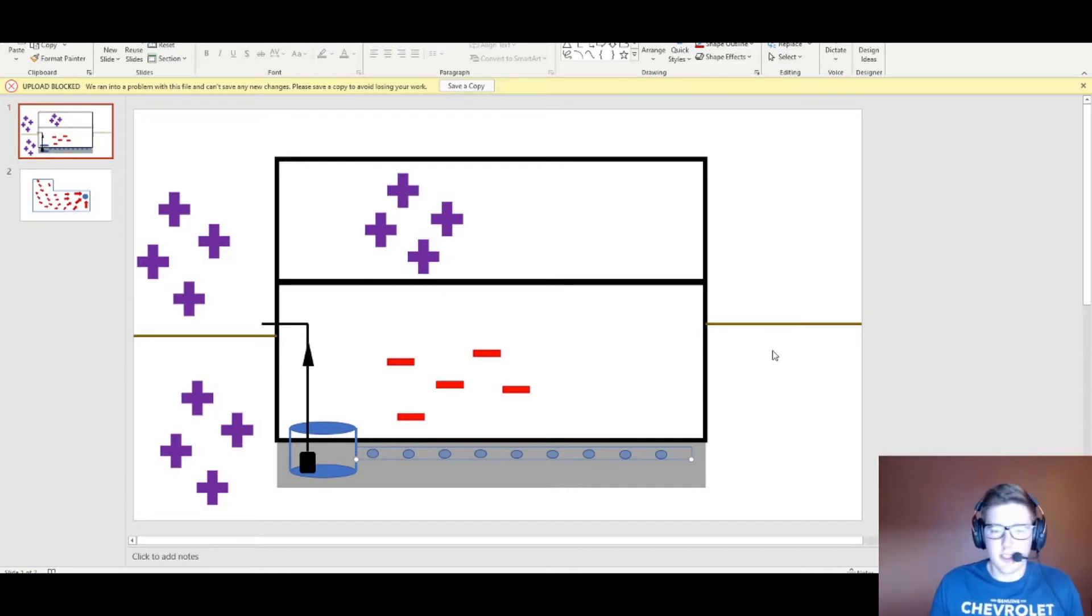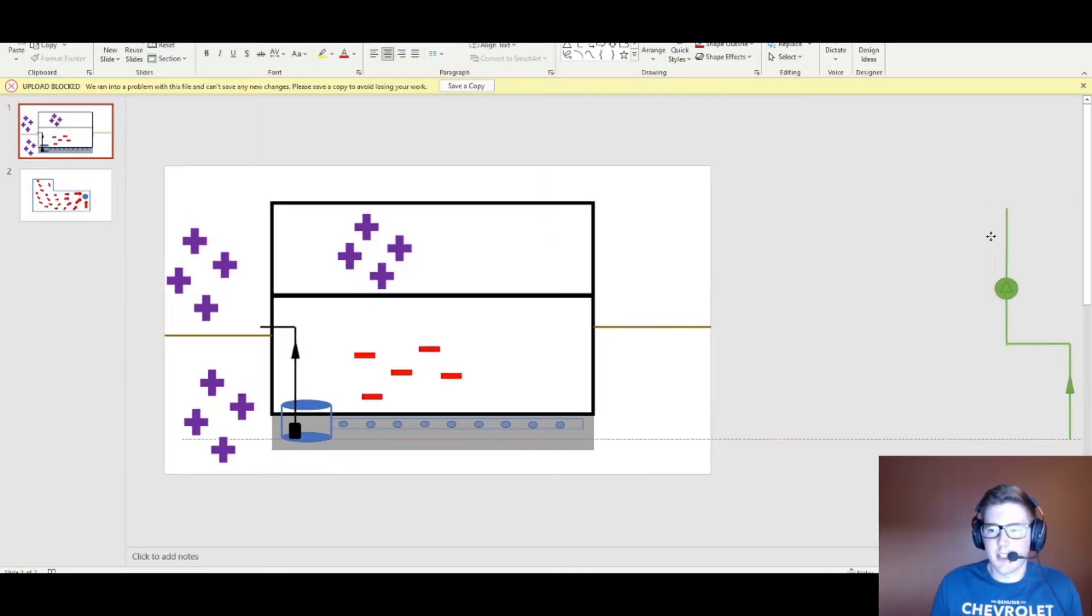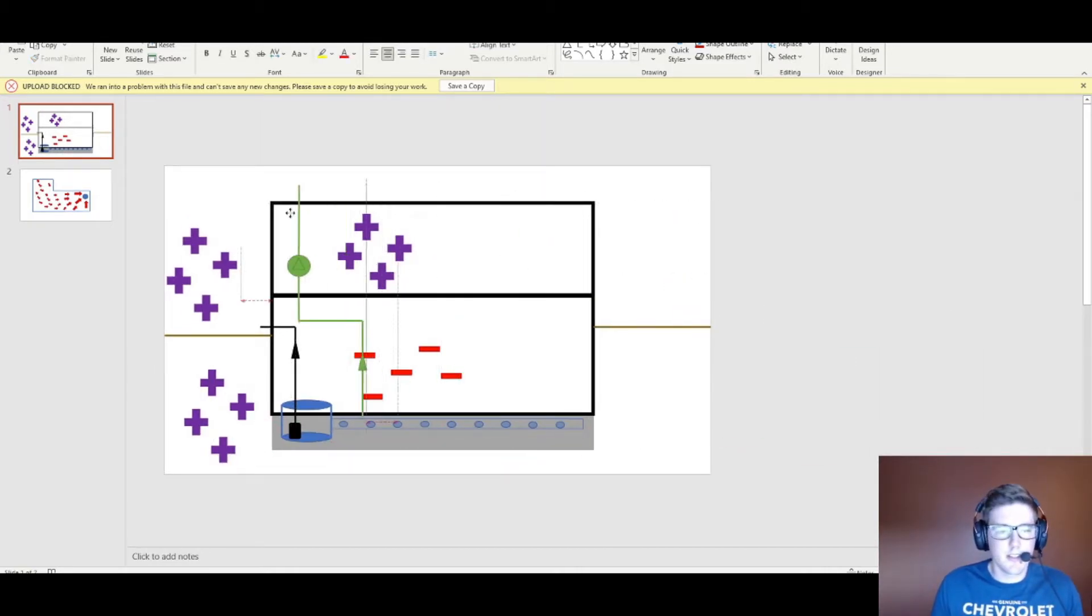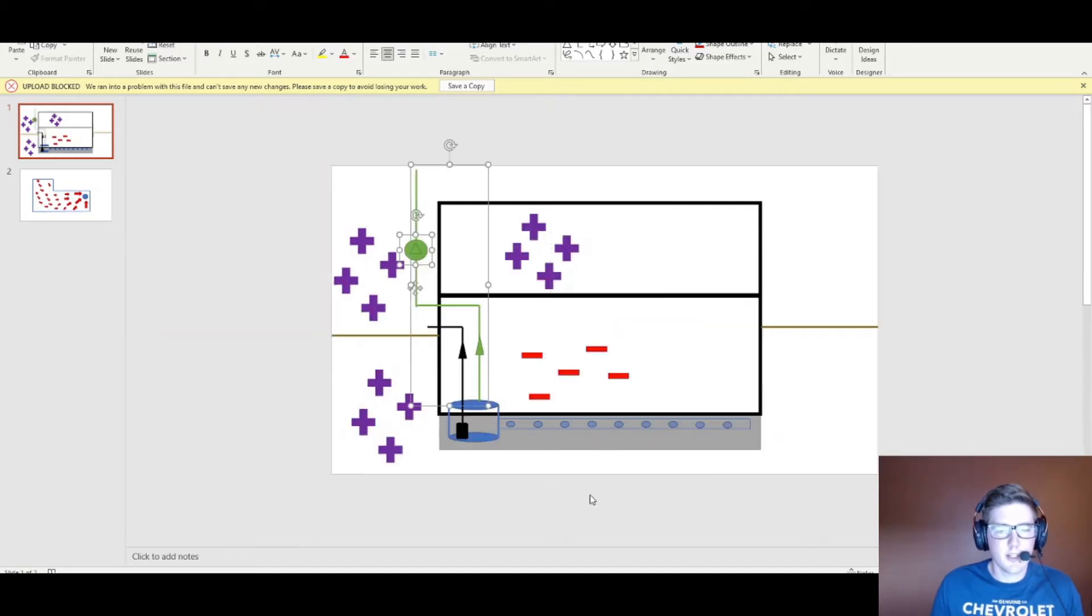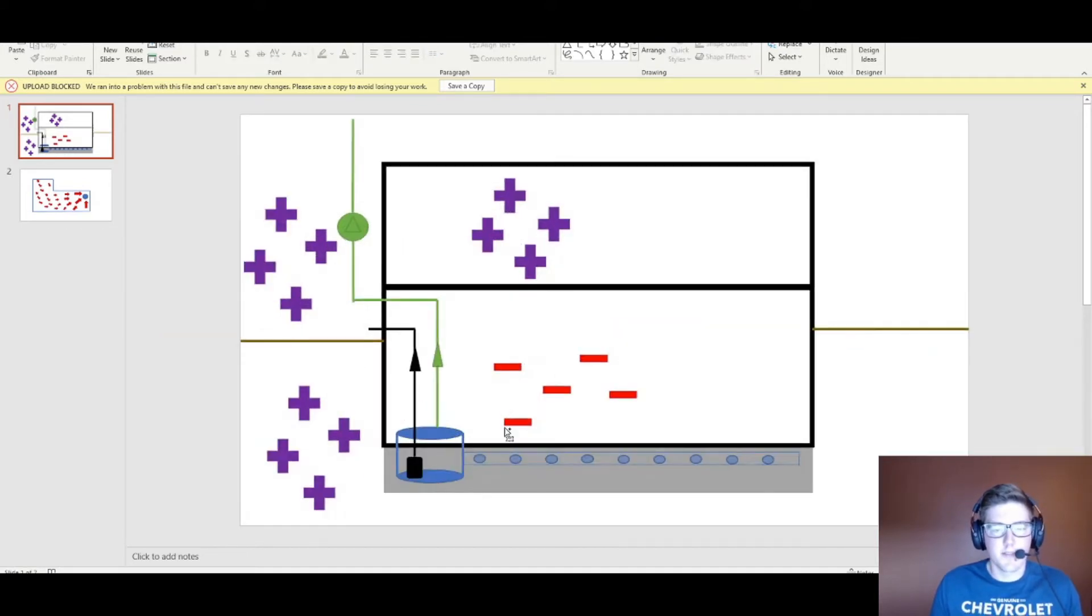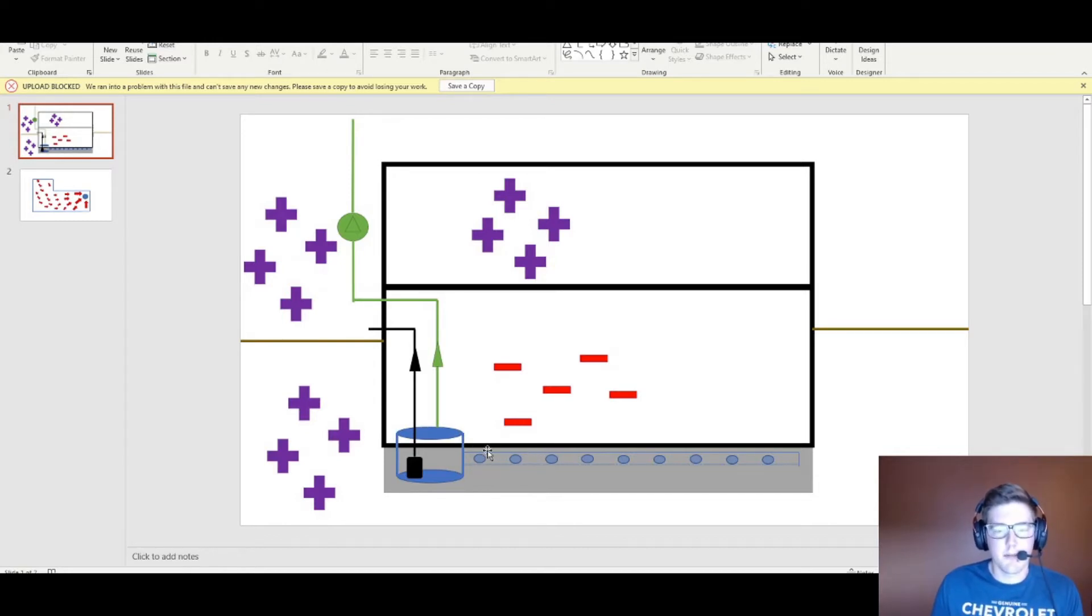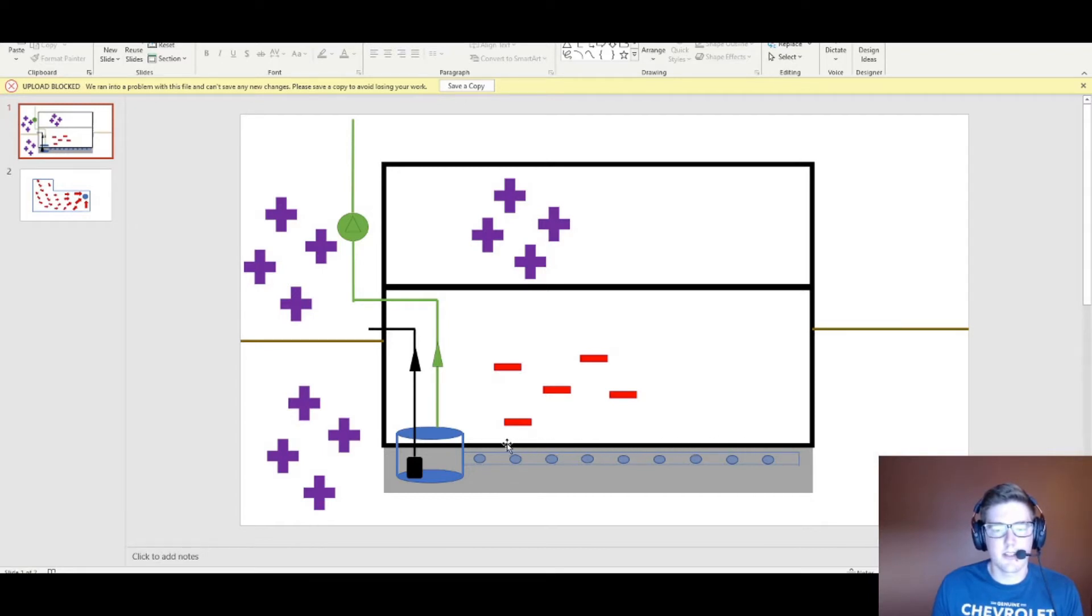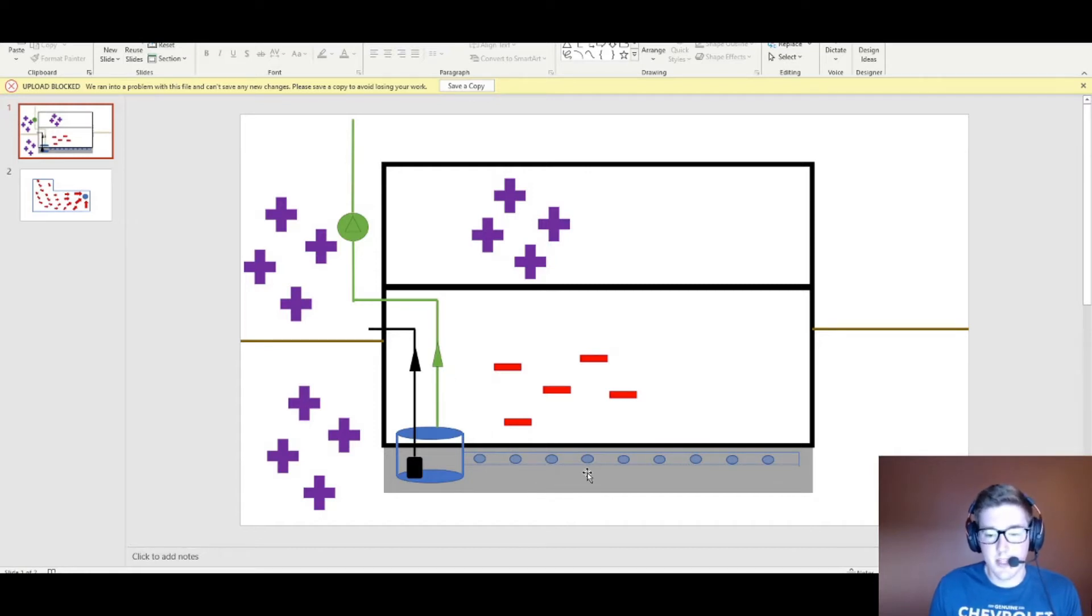Well we're going to install a radon mitigation system with these high-tech graphics. We're going to start off by first capping the sump pit airtight and we're going to seal any big major cracks in your poured slab to help create an airtight seal that we're going to then negatively pressurize underneath that, or sub-slab.